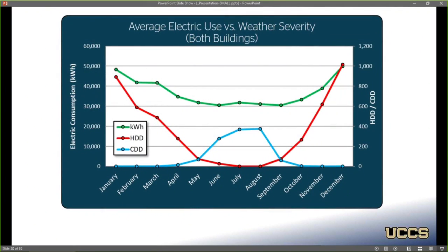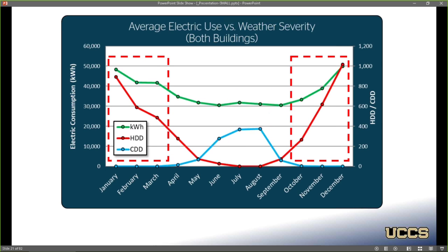And here we have the average monthly electric use plotted against the average monthly heating and cooling degree days, and you can see a correlation between the weather and the electric use. There isn't much of a gain in the summer months. You can see a little blip here in July and August. Maybe not as much of a rise in electric use as you might normally expect, but it's probably skewed by the use of the lab facility, which is a constant volume reheat system. But you can definitely see a correlation between heating degree days and electric use in the winter months.